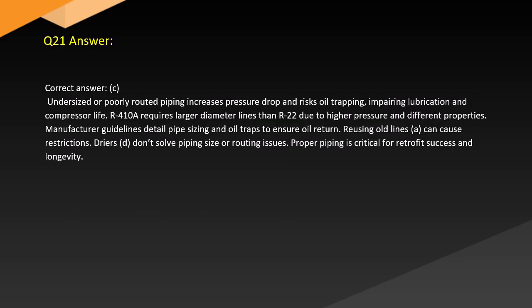Answer. Correct answer. C. Undersized or poorly routed piping increases pressure drop and risks oil trapping, impairing lubrication and compressor life. R-410A requires different line sizing than R22 due to higher pressure and different properties. Manufacturer guidelines detail pipe sizing and oil traps to ensure oil return. Reusing old lines, A, can cause restrictions. Driers, D, don't solve piping size or routing issues. Proper piping is critical for retrofit success and longevity.